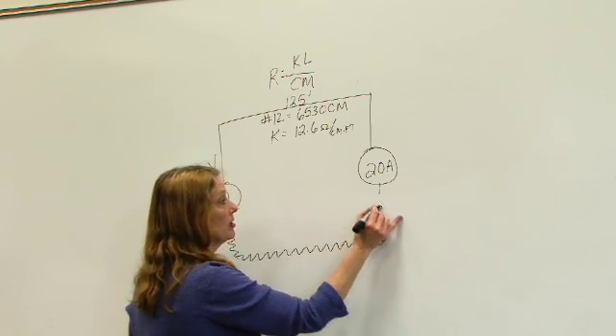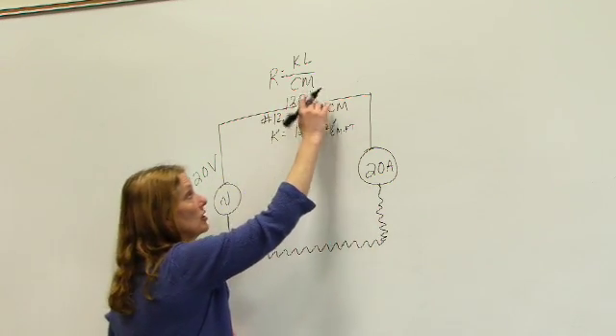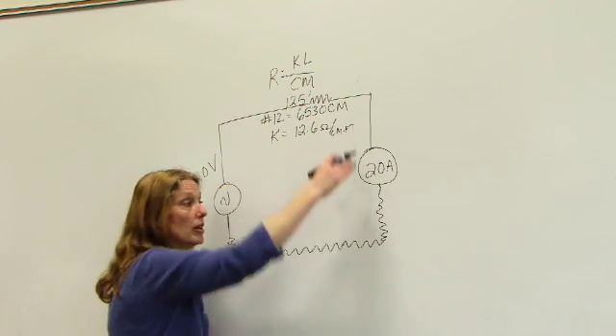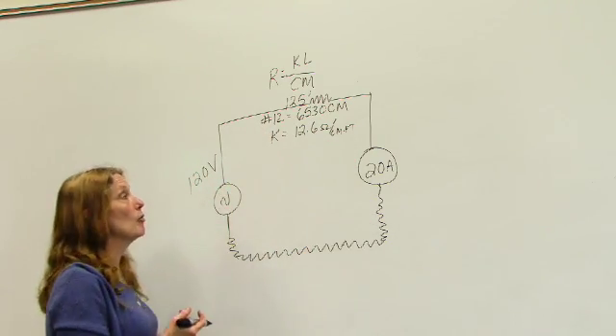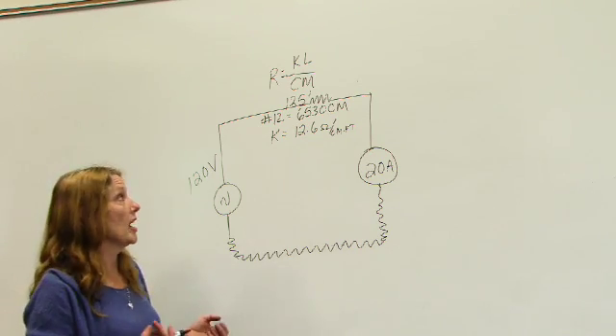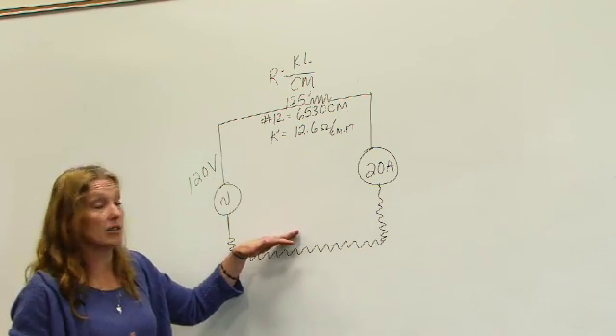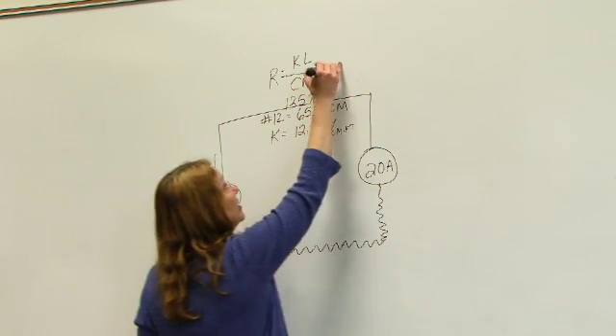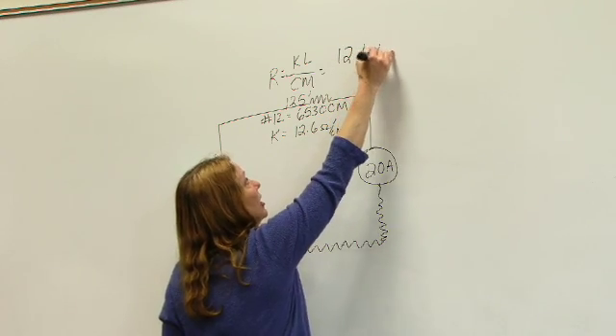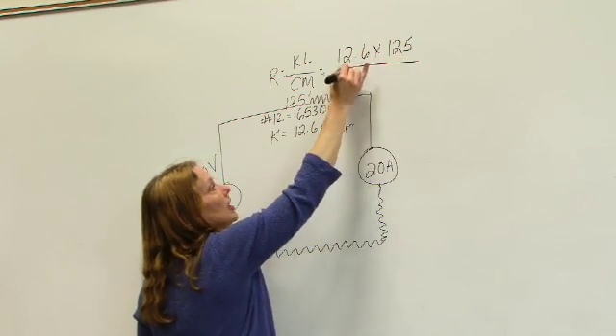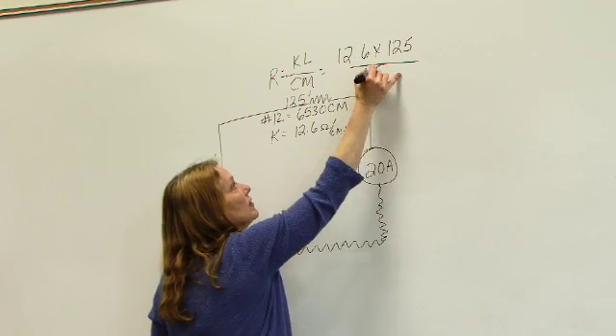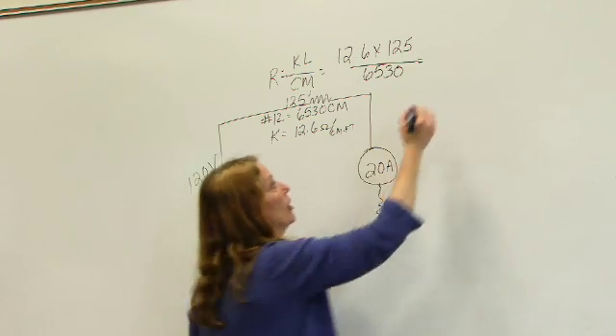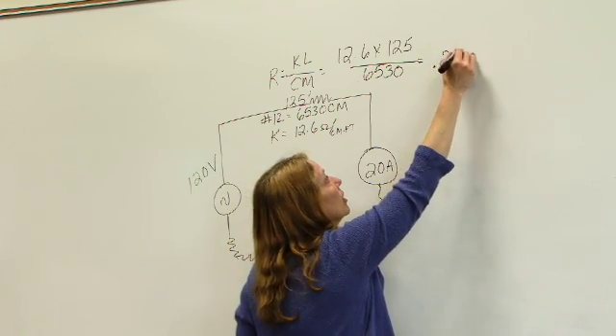We have all the resistance here, same thing here. We have resistance that's traveling throughout from our source to our load coming back. So let's figure out what kind of resistance we have for this wire and this wire because it is additive in this circuit. So if I take and plug this into my formula taking 12.6 times 125 feet divided by 6530, I'm able to come up with a resistance value of 0.241 ohms.